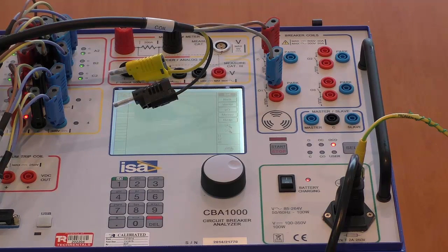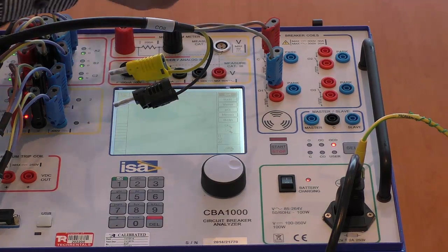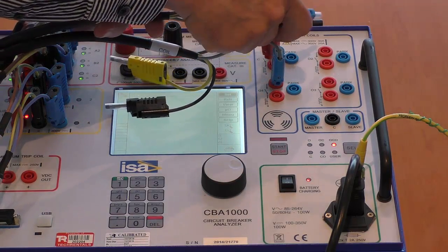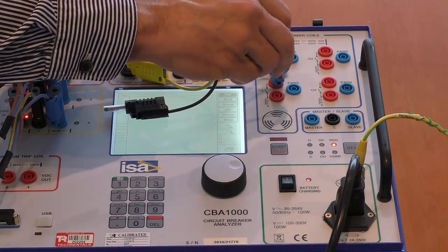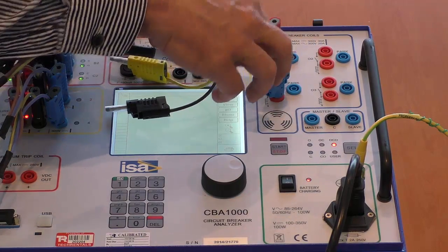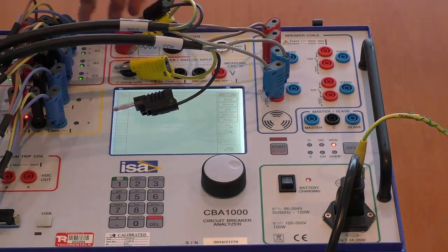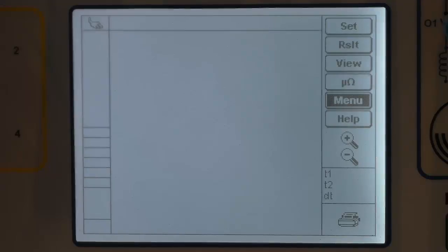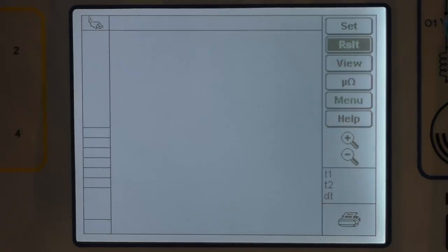In order for the instrument to switch the DC through to the close or the open coil, the other close and open terminals are provided to the terminal block, which lead to the close and the open coils. In order to control the menu, you can spin the dial. In order to select a menu item, you can click the dial.